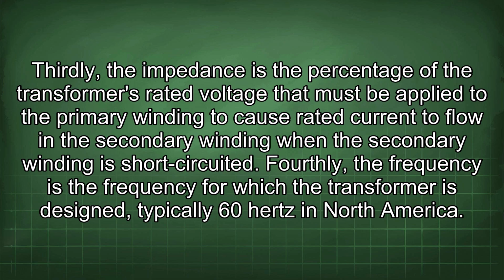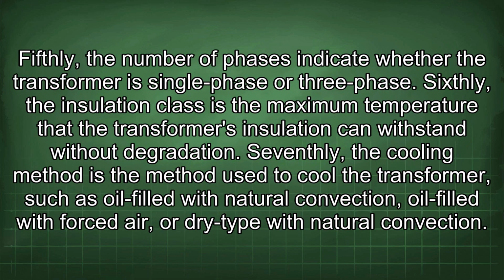Fourthly, the frequency is the frequency for which the transformer is designed, typically 60 Hz in North America. Fifthly, the number of phases indicates whether the transformer is single-phase or three-phase. Sixthly, the insulation class is the maximum temperature that the transformer's insulation can withstand without degradation. Seventhly, the cooling method is the method used to cool the transformer, such as oil filled with natural convection, oil filled with forced air, or dry type with natural convection.